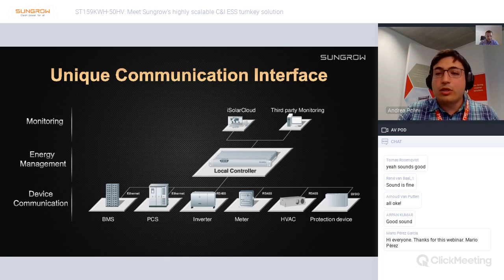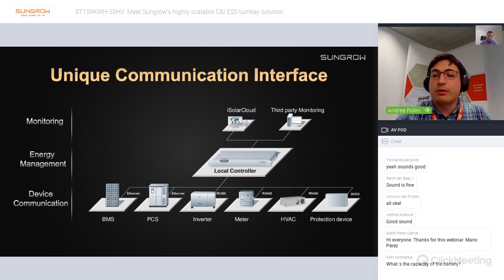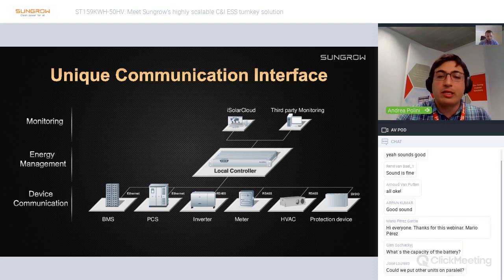The local controller is the unique communication interface between the components of the ESS and the customer's energy management system. It gets information from the Samsung battery management system, can send commands to the power converter, and is connected to the energy meters to operate in various intelligent modes. On the customer side, it connects to the customer's EMS through the open Modbus TCP protocol interface that we provide to all partners and customers who want to interface with our system. The customer's EMS can easily control the ESS, for example in peak shaving mode or other smart operation modes that include control of the whole energy system.